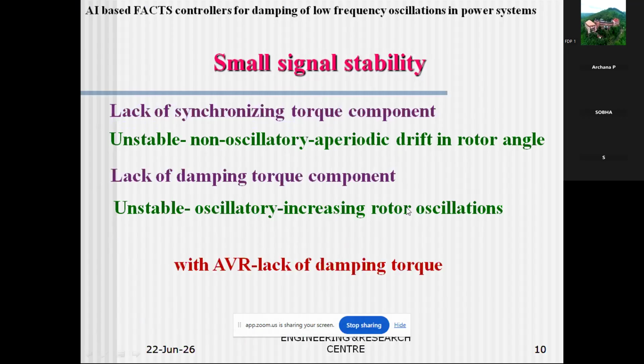And usually, when a system is working with an automatic voltage regulator, there will be enough synchronizing torque in the system, but there will be some lack of damping torque. This will be impaired, and modern power systems always work with a fast acting automatic voltage regulator, the AVR. So as a result, there is always a threat to the damping torque component. That means that when it is working with fast acting automatic voltage regulators, the system is likely to have increasing rotor oscillations for small changes in the system. So this is where a lot of techniques are involved.